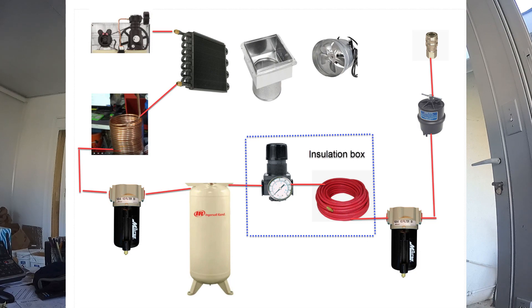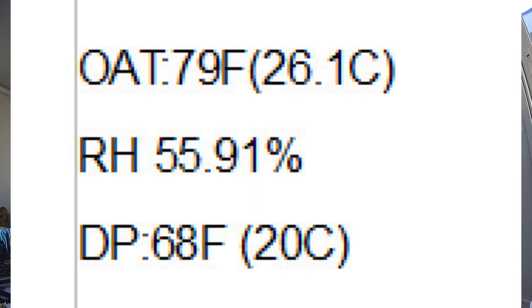We will evaluate our system for the following weather conditions: 79 degrees Fahrenheit, relative humidity 55.9%, and a dew point of 68 degrees Fahrenheit — kind of a typical Florida day. Our design parameters are: a 30 gallon tank, compressor output temp range of 250 to 300 degrees Fahrenheit. We will regulate segment two tank pressure between 155 and 110 psi for an average pressure of 132.5 psi. This results in the following maximum temperature gradients for each segment. These gradients will only occur if the CAT is cooled to the outside air temperature.